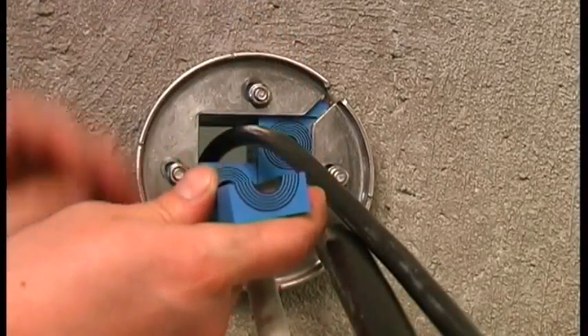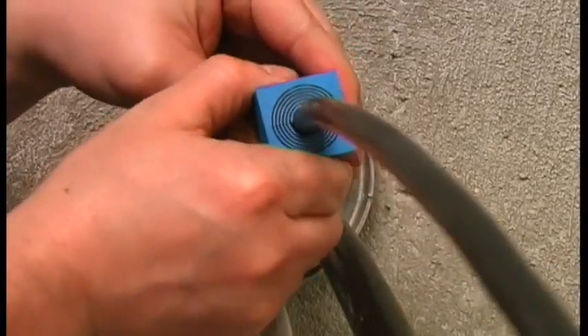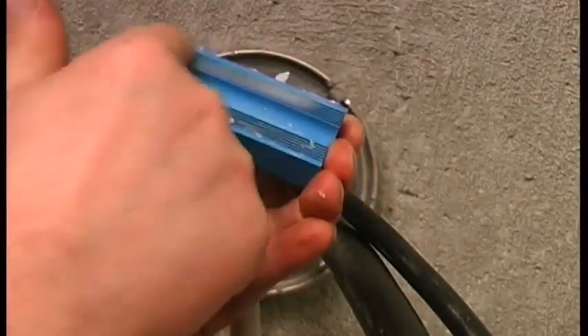Adapt the module to the right cable diameter and make sure that there is a 0.1 to 1 millimeter gap. Lubricate thoroughly and then reinstall the module.